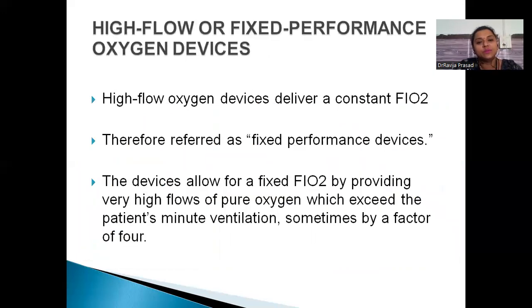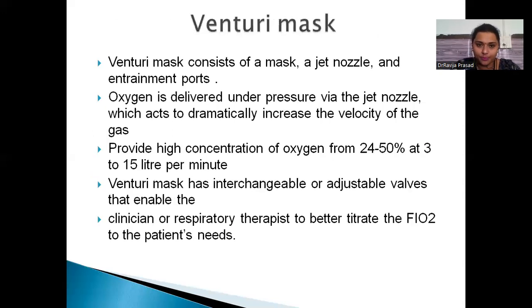Now, the high flow or fixed performance oxygen devices. The high flow oxygen devices deliver a constant FiO2, therefore they are referred to as fixed performance devices. The device allows for a fixed FiO2 by providing a very high flow of pure oxygen, which exceeds the patient's minute ventilation, sometimes by a factor of 4.